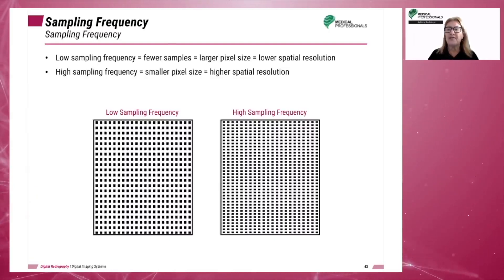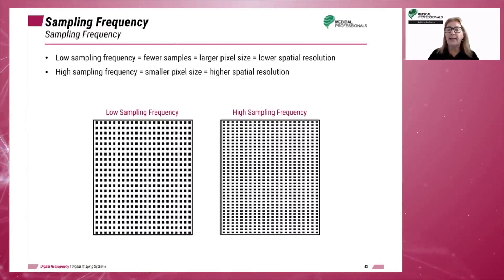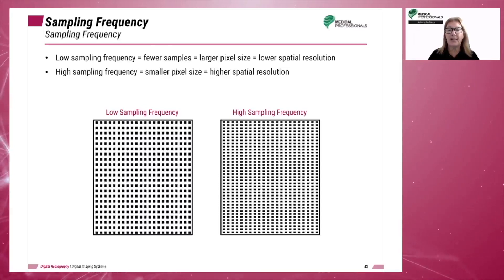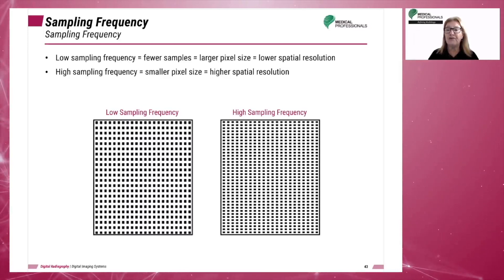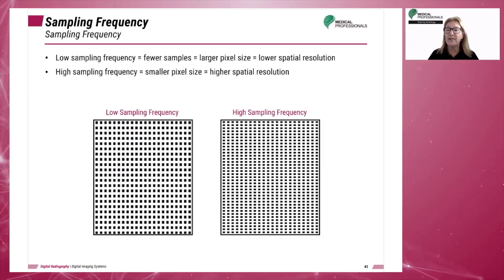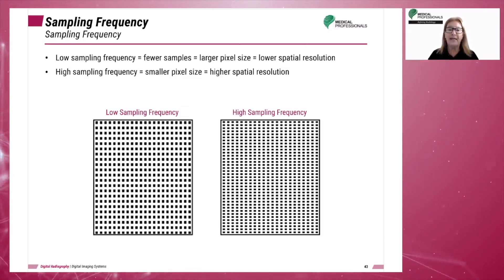Sampling frequency is the number of pixels sampled per millimeter. It controls spatial resolution in computed radiography. More pixels sampled means increased spatial resolution. However, sample frequency can change from vendor to vendor, varying from 5 pixels per millimeter to 20 pixels per millimeter. The choice of sample frequency is based on the plate size and you may be able to select that from the main menu.